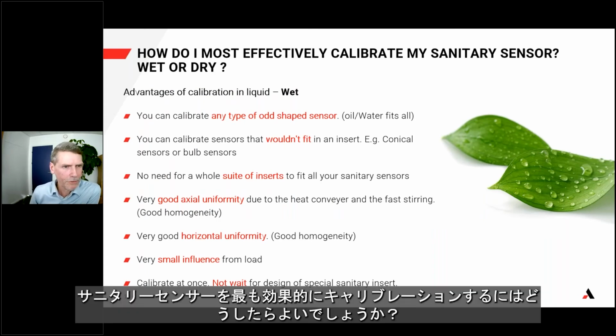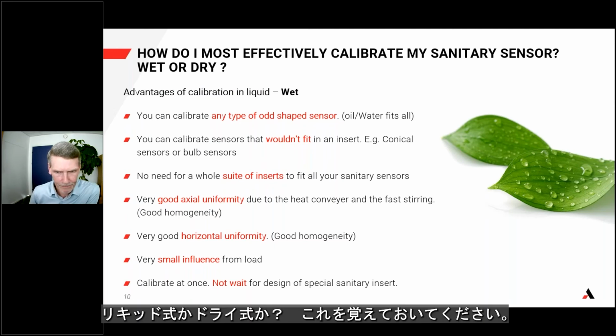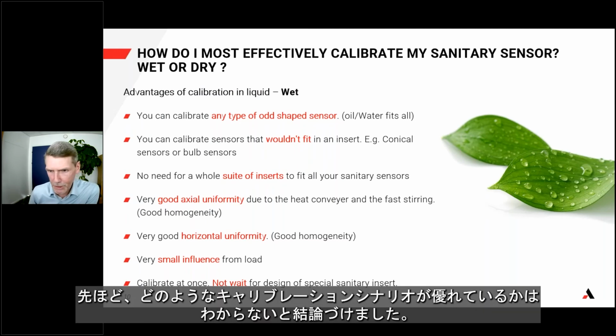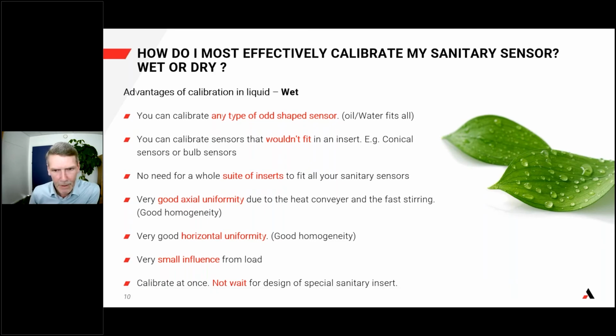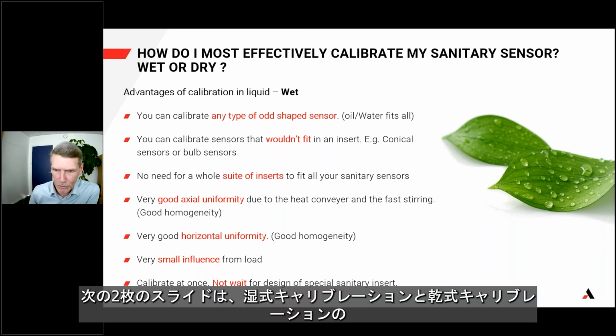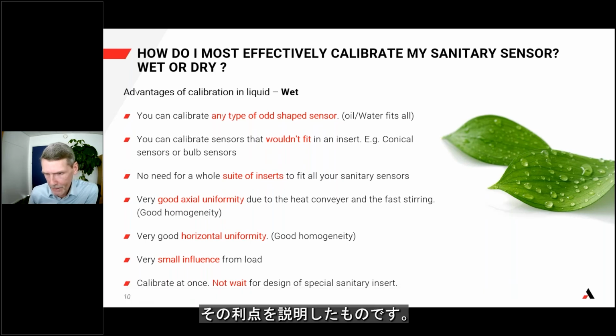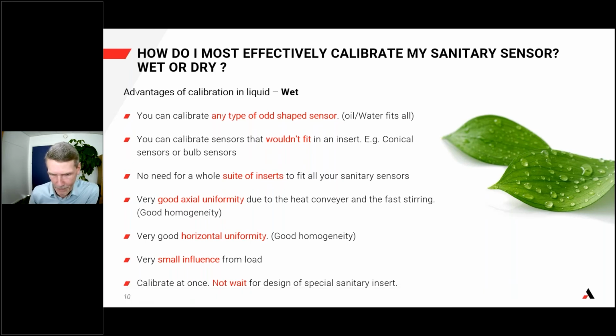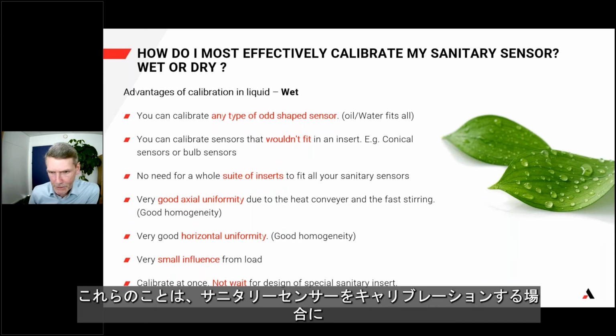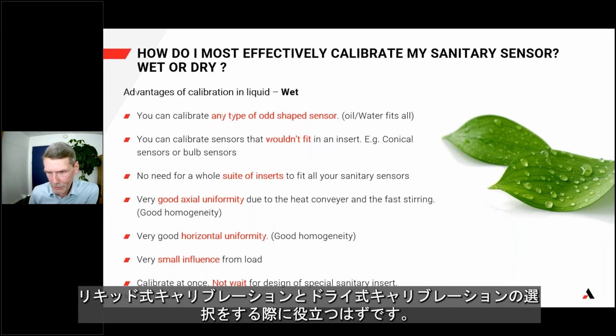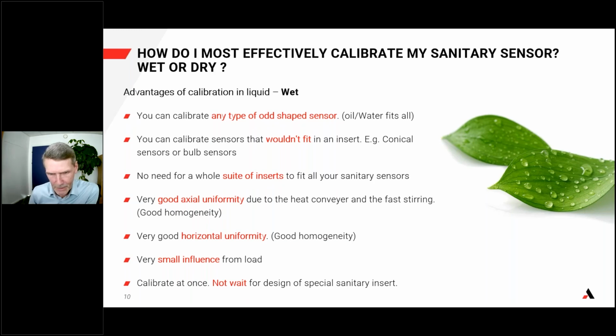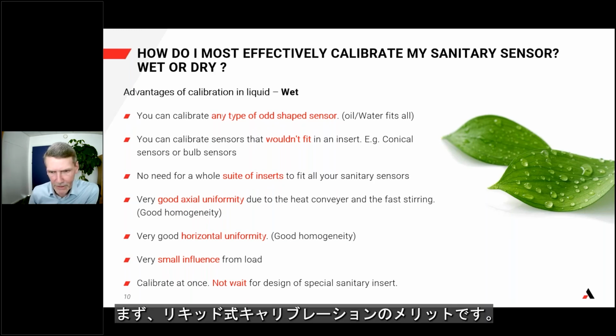How do I most effectively calibrate my sanitary sensor, wet or dry? Remember, we just concluded that no calibration scenario is better than the other. The next 2 slides are just describing advantages of wet and dry calibration. These should help you to make your choice between wet and dry calibration for your sanitary sensor calibration. So first of all, here are the advantages for wet calibration.